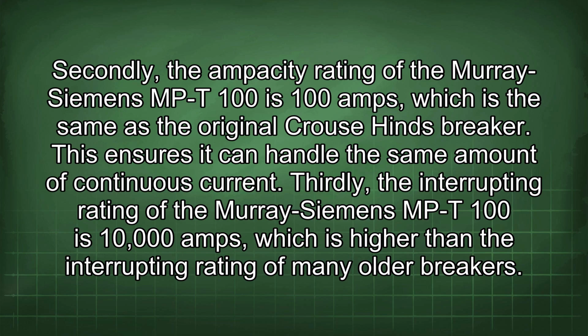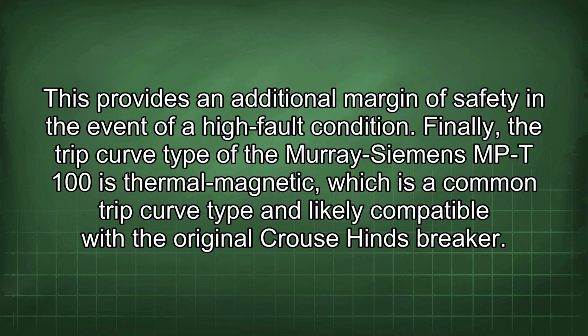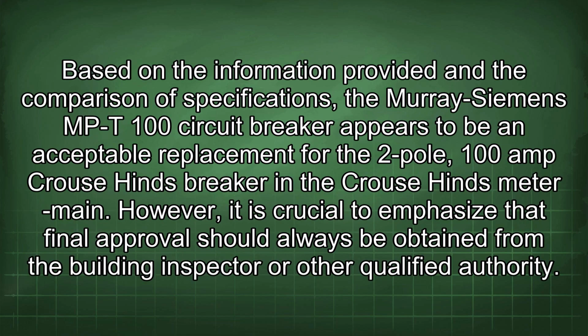Thirdly, the interrupting rating of the Murray-Siemens MP-T 100 is 10,000 amps, which is higher than the interrupting rating of many older breakers. This provides an additional margin of safety in the event of a high fault condition. Finally, the trip curve type of the Murray-Siemens MP-T 100 is thermomagnetic, which is a common trip curve type and likely compatible with the original Crouse Hinds breaker. Based on the information provided and a comparison of specifications, the Murray-Siemens MP-T 100 circuit breaker appears to be an acceptable replacement for the 2-pole, 100 amp Crouse Hinds breaker in the Crouse Hinds meter main.